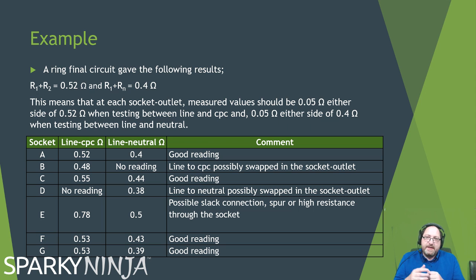So we've got here sockets A, B, C, D, E, F and G. Socket A, the line to earth test 0.52, the line to neutral test 0.4, bang on with the top readings. So it's a good reading. With socket B, we had 0.48, which is within 0.05 tolerance of 0.52. That's fine. We had no reading from line to neutral. Now if I have a measurement between line and earth, and I have no measurement between line and neutral, it could be that line and earth, while I had a measurement there, in the socket outlet may have been swapped around. Because to have nothing between line and neutral, but something between line and earth, suggests that line and earth are the wrong way around. Okay.